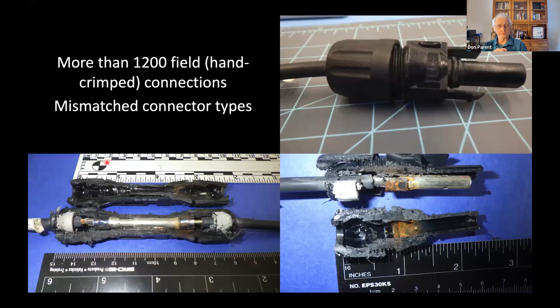And here, in the upper right-hand corner, you see a connector back shell that's cross-threaded. So this connector here would not have been watertight. And this connector down here has evidence of corrosion. And corrosion in an electrical connection results in increased resistance. If you have 8 amps going through a corroded connector and its resistance is increasing, you get more power as the resistance goes up. So basically, you end up with high resistance, which produces high power. That high power creates high temperature. High temperature creates increased resistance, and you end up in a thermal runaway condition potentially. So with increasing resistance comes increasing temperature, which causes increasing resistance. I think you get the point there.